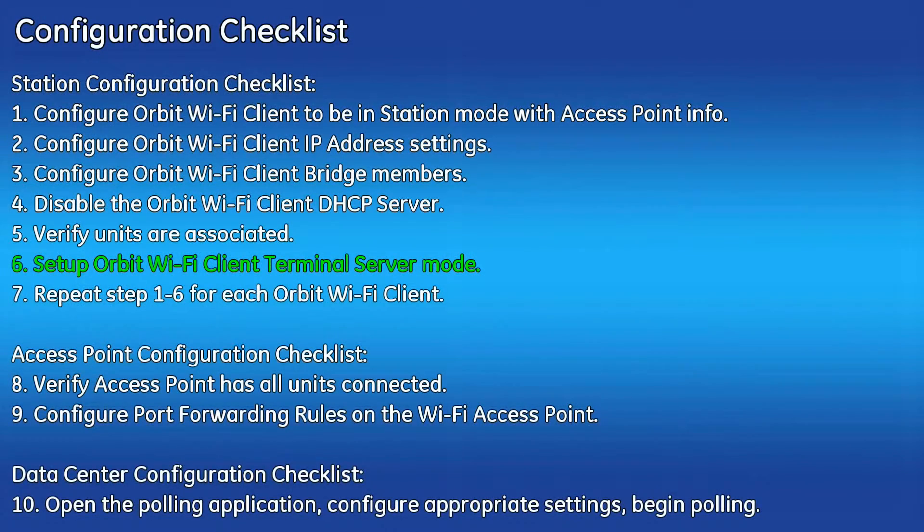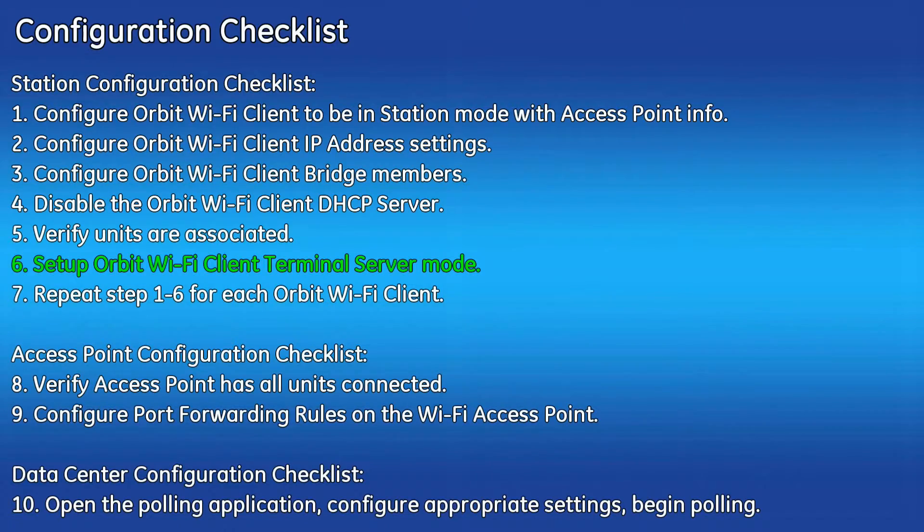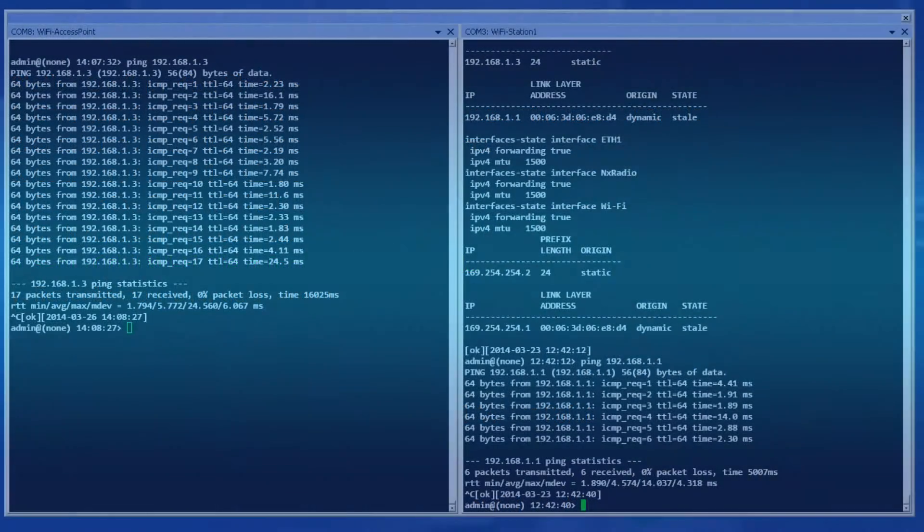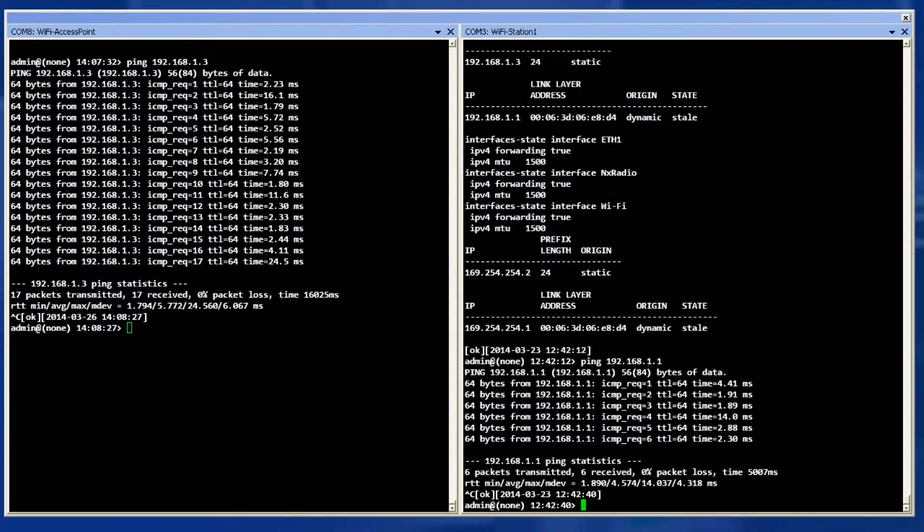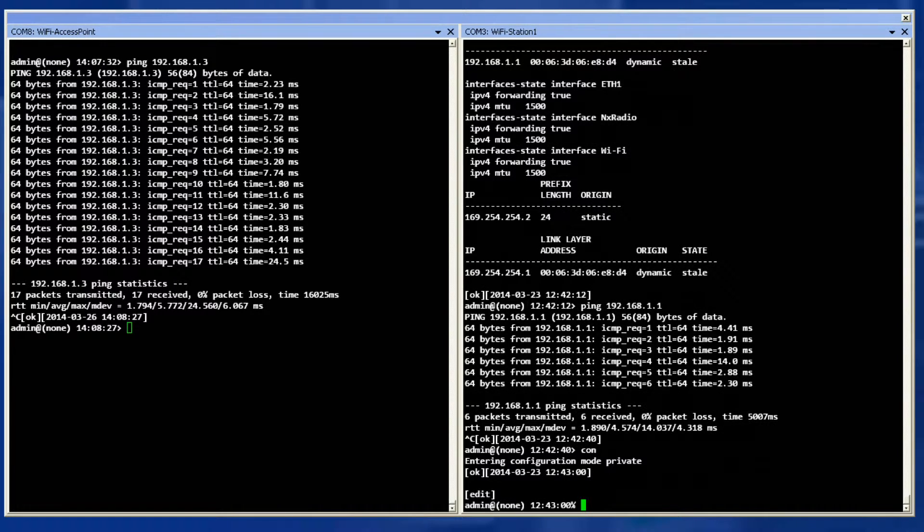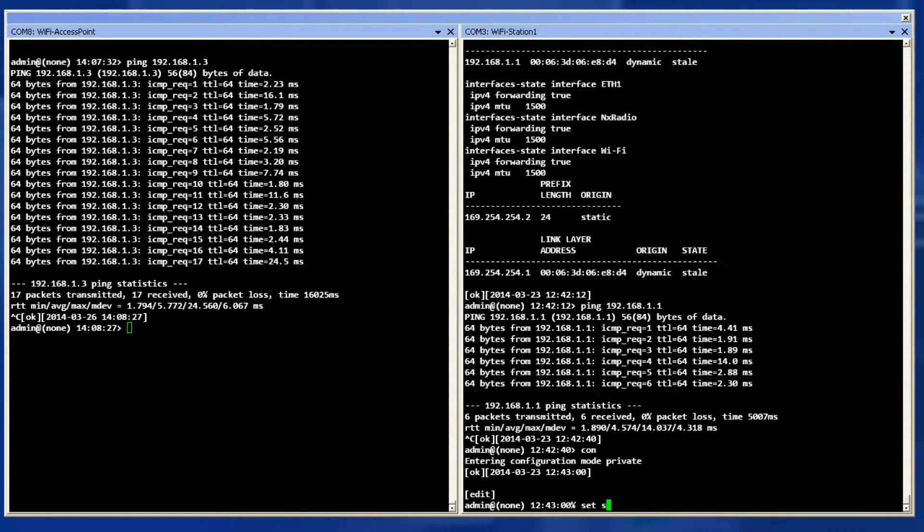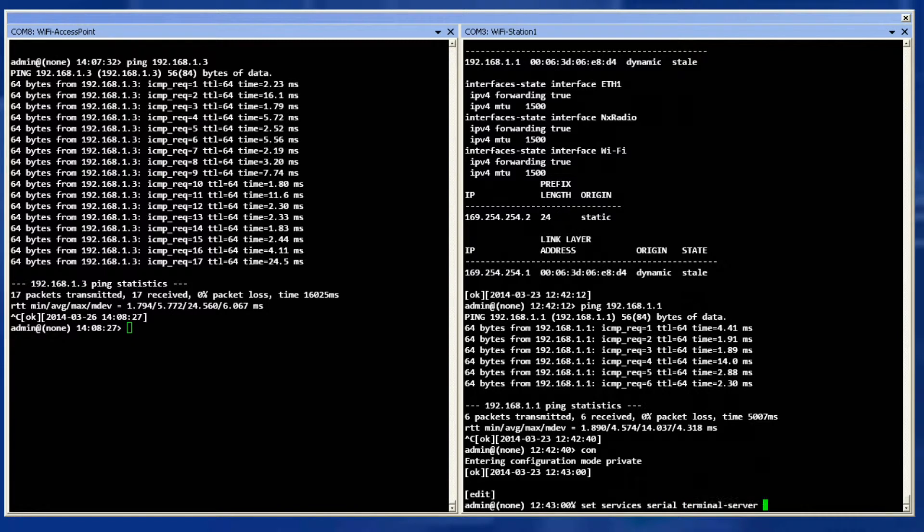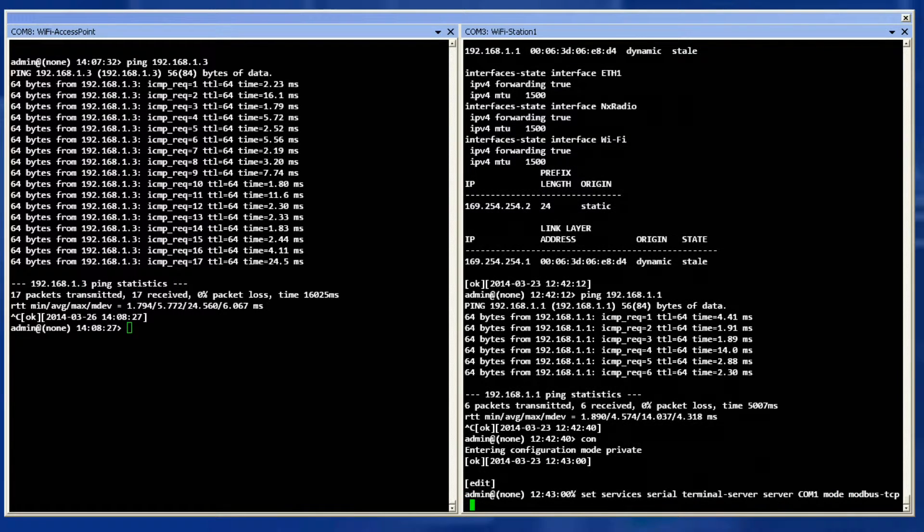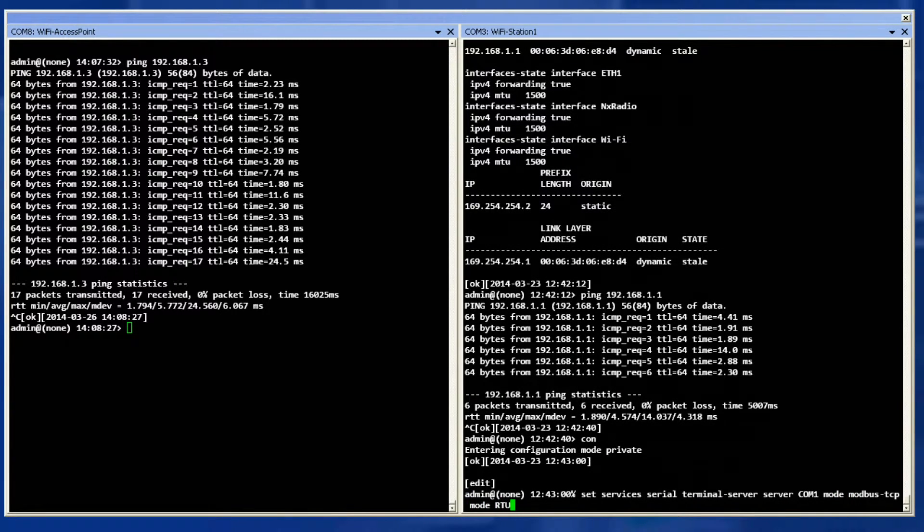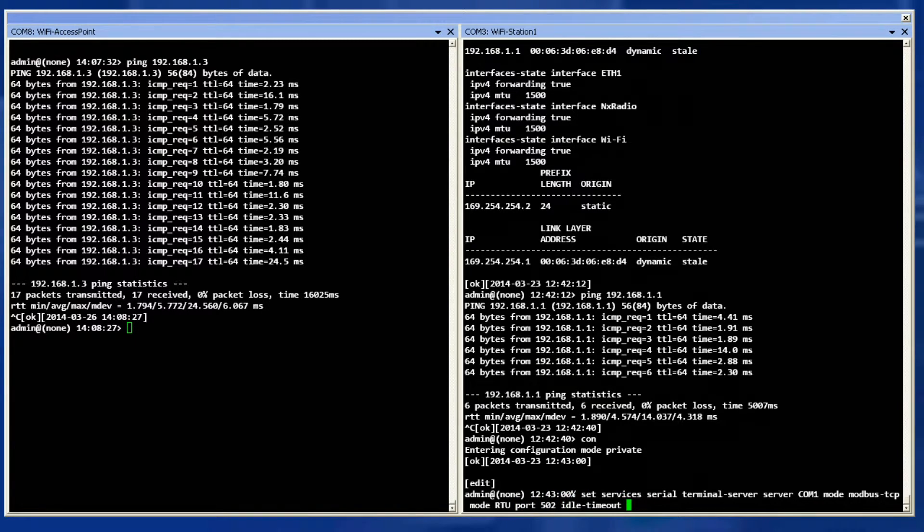Step six is to set up the Orbit Wi-Fi client terminal server mode. Enter configuration mode and enter the set command displayed to turn one of the serial ports into a terminal server. You may use the COM1, COM2, or the USB1 port as a terminal server. Choose this parameter as best fits into your system. This configuration will use COM1 and will be set to Modbus TCP mode listening on port 502 using RTU mode.